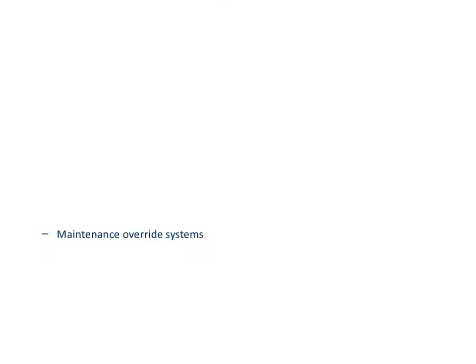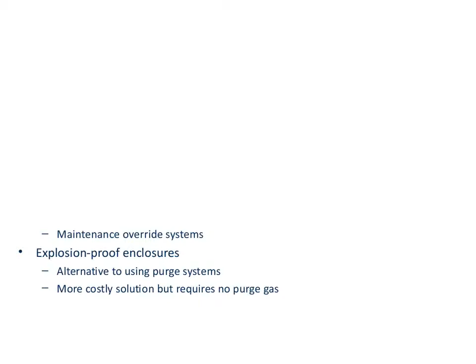And if for some reason purging is not an option, perhaps you're mounting the equipment where purging air is not available, they make explosion-proof boxes, big, thick aluminum enclosures, where it literally assumes that if the analyzer does explode, it's all contained within that box. So these are certainly an option. They tend to be a little bit more expensive and obviously a lot more cumbersome to do maintenance on, but they are an option.